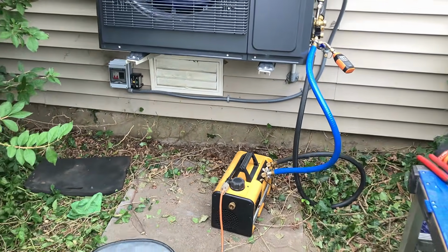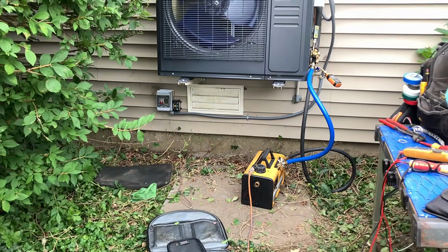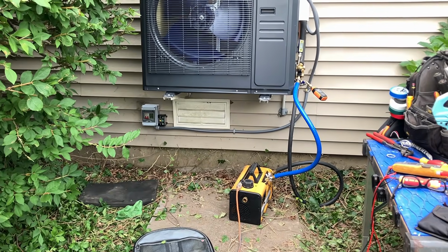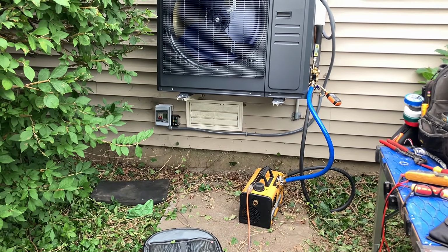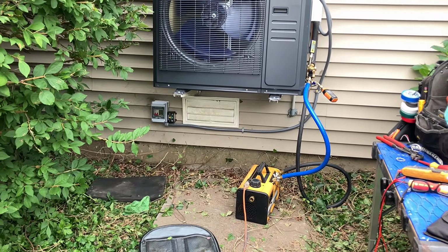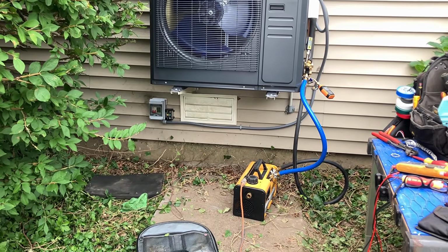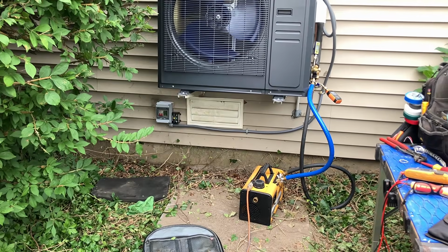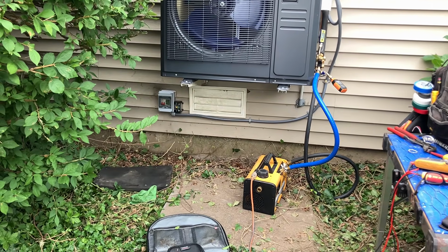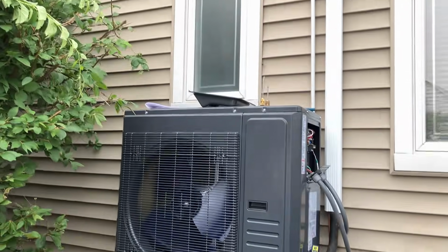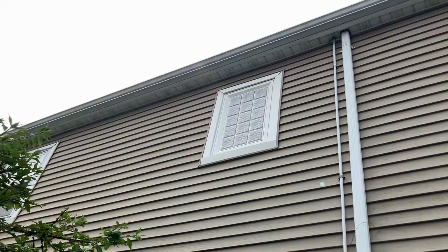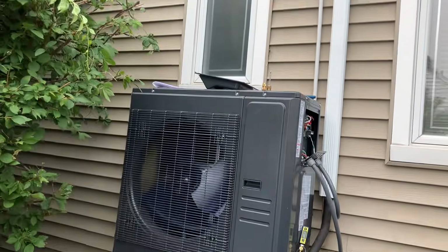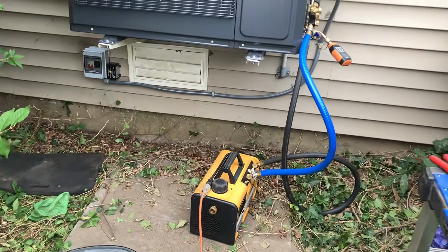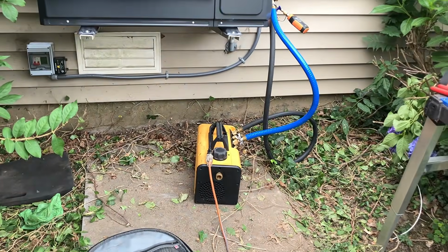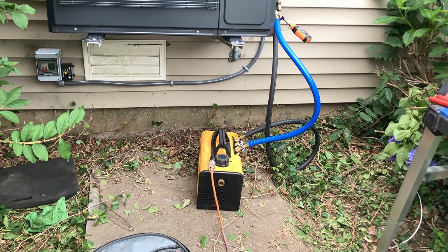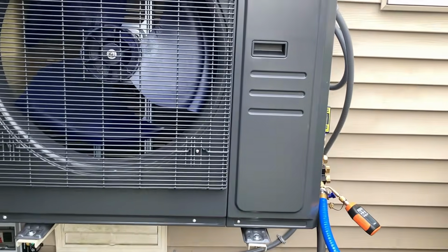I know I talk about this in almost all of my installation videos, but we're at one of the most critical steps of any HVAC installation, and that's called the evacuation process. And yes, I know I talk about this in almost every install video, but that's because it's that important. When these refrigeration lines are open to the atmosphere, moisture and air get inside. And air doesn't belong in a refrigeration system. And moisture, it's even worse. Moisture combines with the refrigerant and the compressor oil, forms acids that attack the windings of the internal components like the compressor.